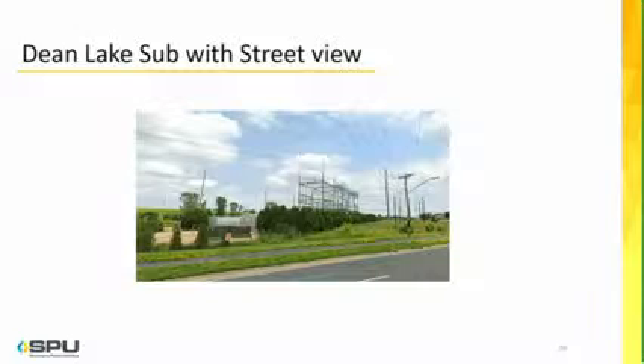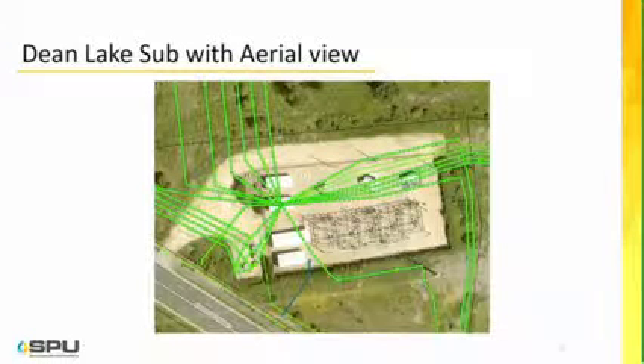It is close to 169, and even though the transmission system is independently operated for the benefit of all the utilities that are using it, it is owned by Xcel Energy in this area, and they had a concern of salt spray coming off of the highway that would coat the insulators, and there might be some flashover on the 115 kV. They had experienced quite a bit of trouble with that in their Parker's Lake substation along 494 in Plymouth, because they're located on the east side in the prevailing winds. So they had to put up a giant netting material to capture that salt spray to keep it from coating the insulators. The salt is conductive and it'll track across the insulators and cause flashovers. And they have to be cleaned periodically.